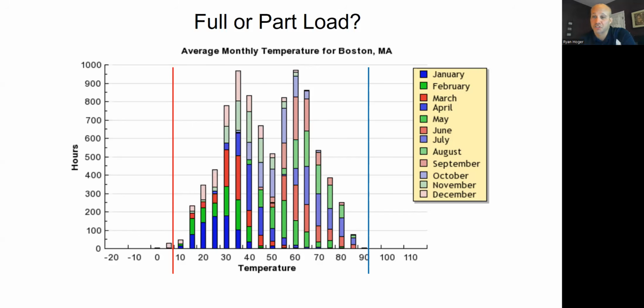So I don't really care how efficient somebody's thing is at 95, right? And that was always our EER number for various types of equipment. It's like, okay, great, you're really efficient at 95, great. I don't care. How efficient are you at part load? Well, with old systems where everything was on off, if you were efficient at full load, 95 degrees, you were equally efficient at other loads, relatively speaking to other equipment. But now with inverter driven technology where I'm speeding up and slowing down compressors, condenser fans, and indoor blowers, I can be more efficient at part load. And that's what really matters.